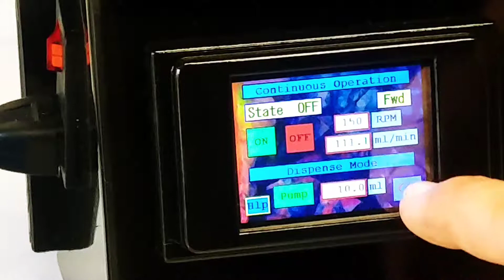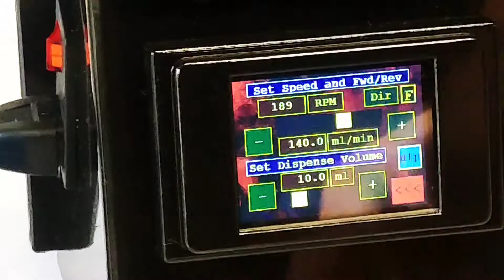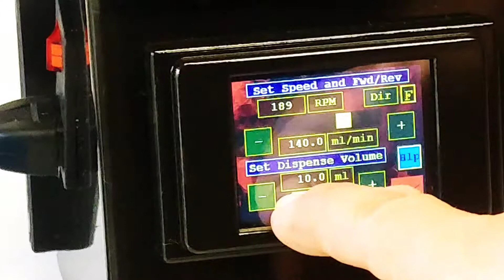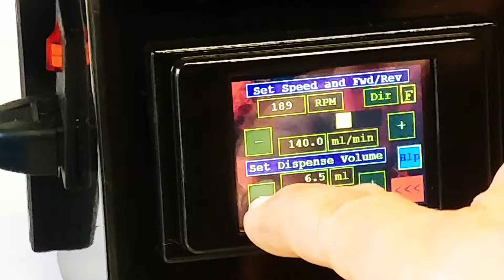We can jump into the setup screen, set the speeds up. Let's set the speed up to about 140 milliliters per minute. And while we're here, set the dose down to, say, I don't know, let's set it down to 5 milliliters. Okay, when we go back into the run screen, you'll see that everything's updated.